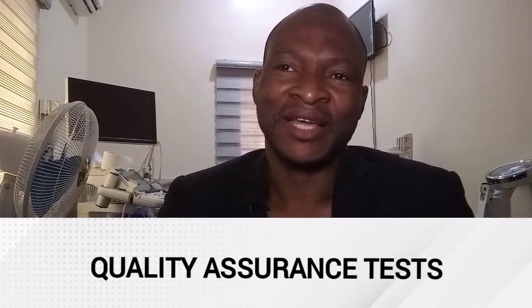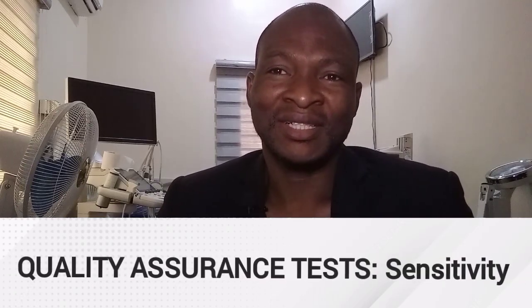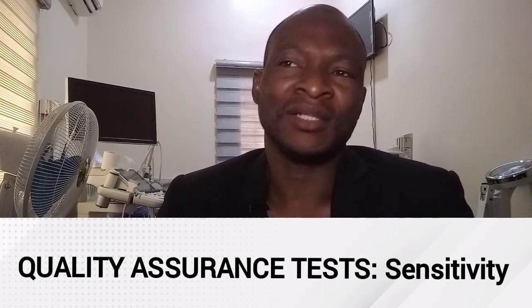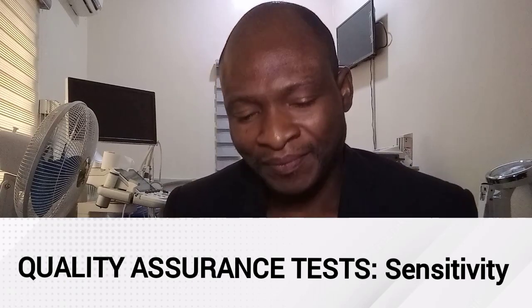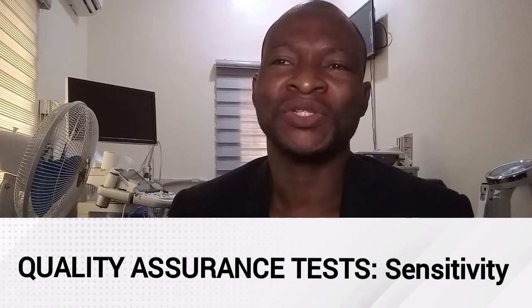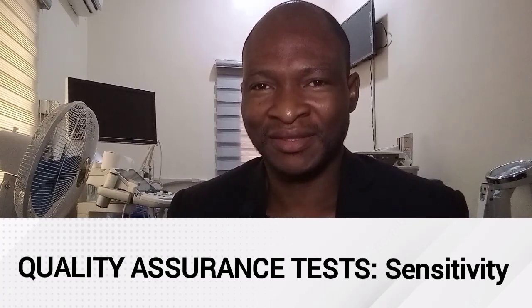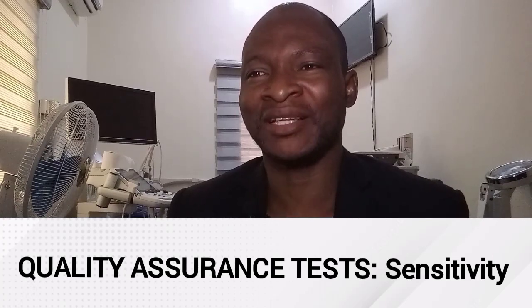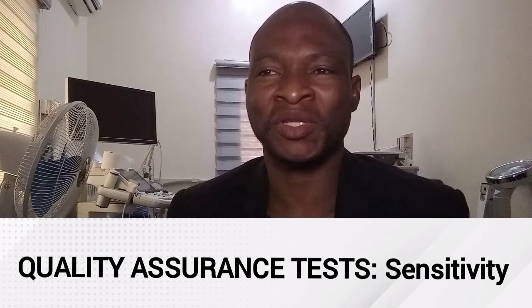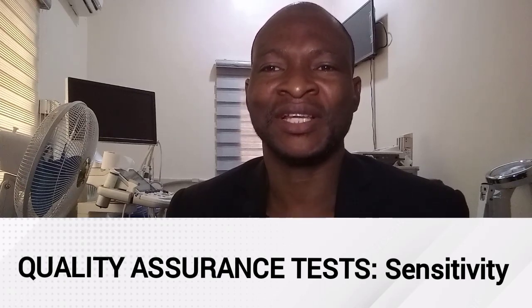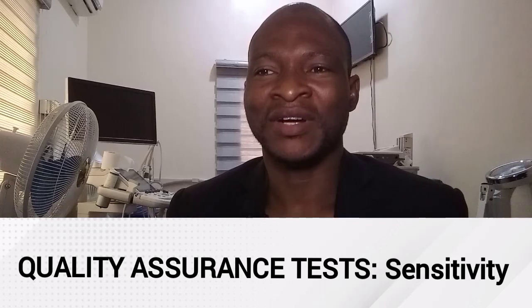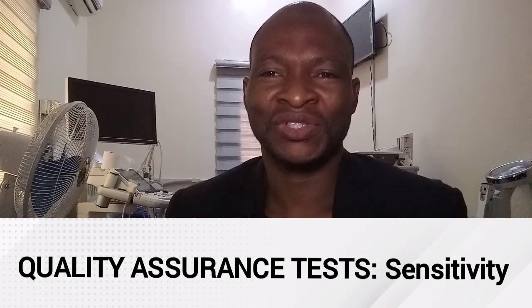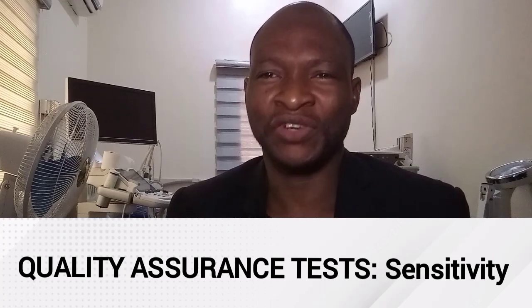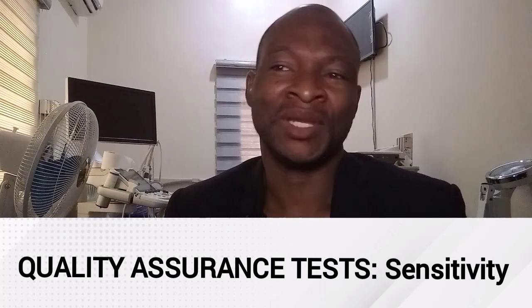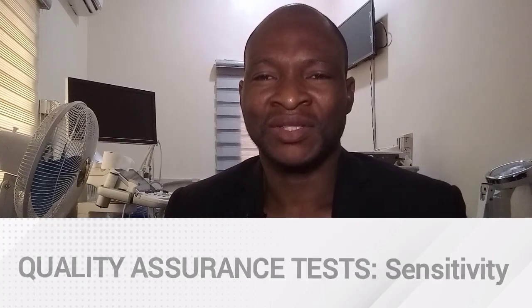Quality assurance tests include sensitivity. Sensitivity is the ability to detect and display weak echoes. Now, when the system is adjusted to display the weakest echo possible, we refer to this as maximum sensitivity. It is a measure of the minimum gain setting required to produce echoes on display from a specific interface. A change of 6 decibels or greater over time indicates a need for service.